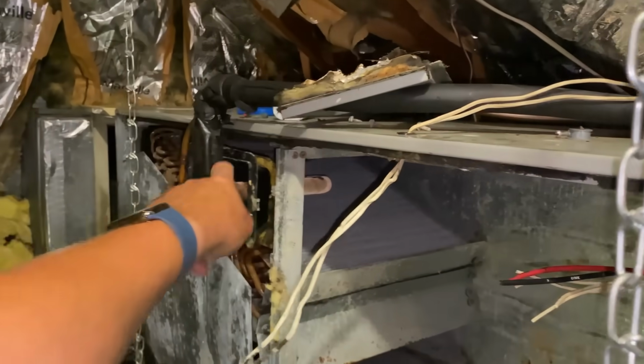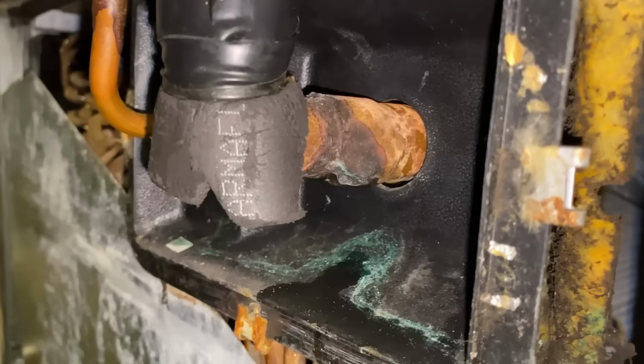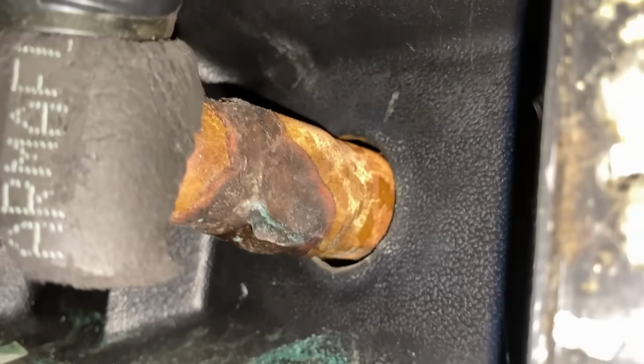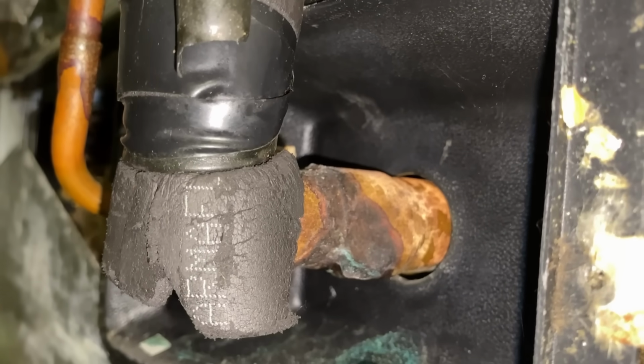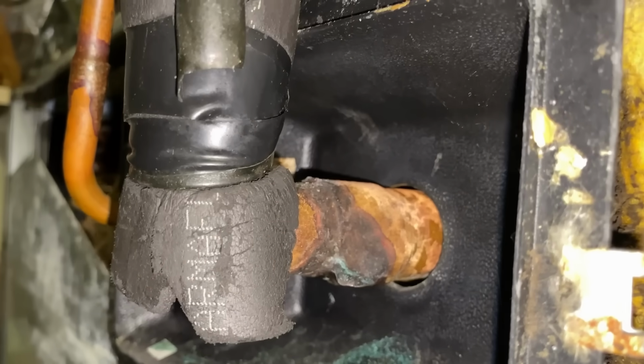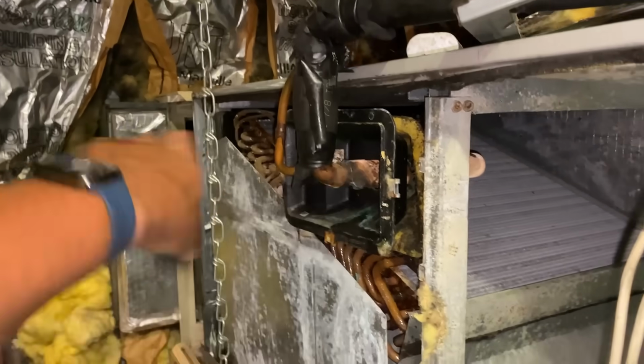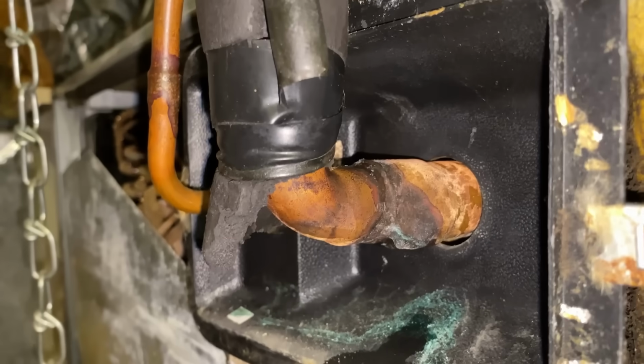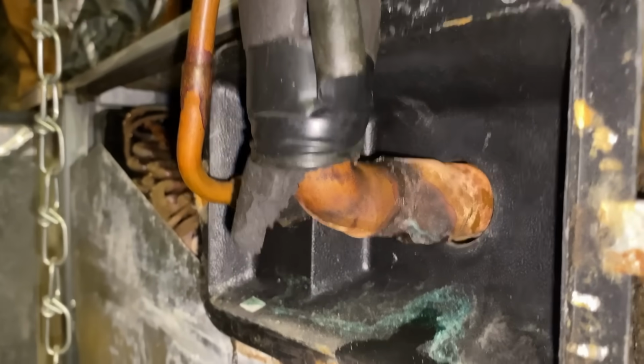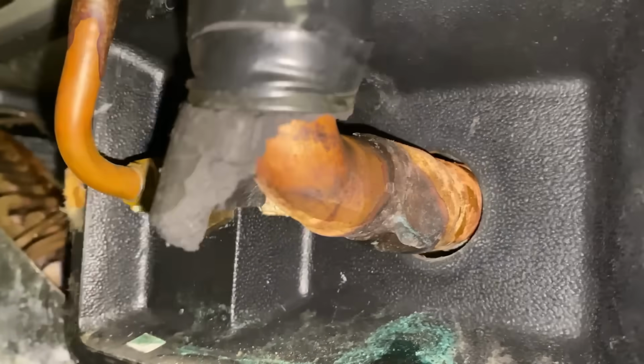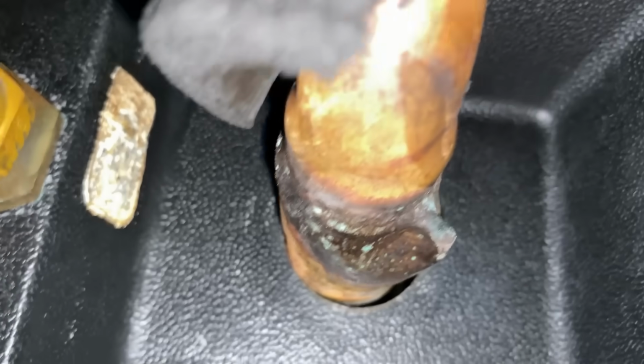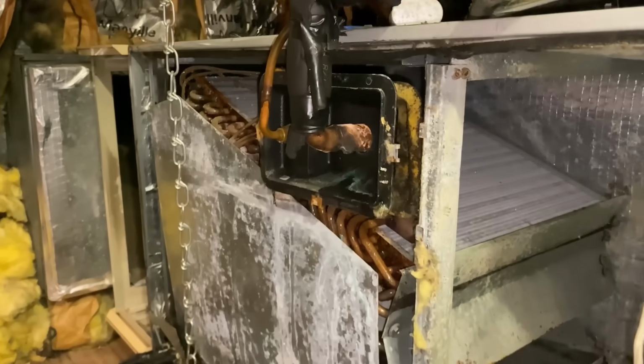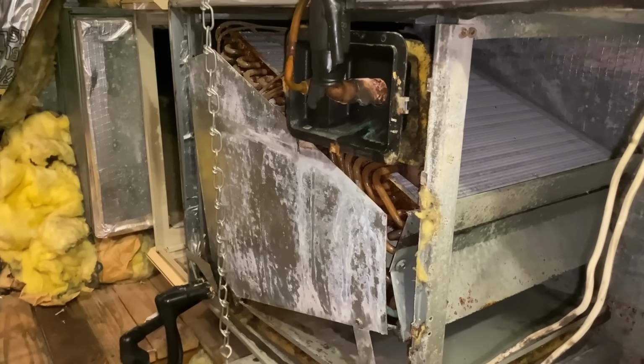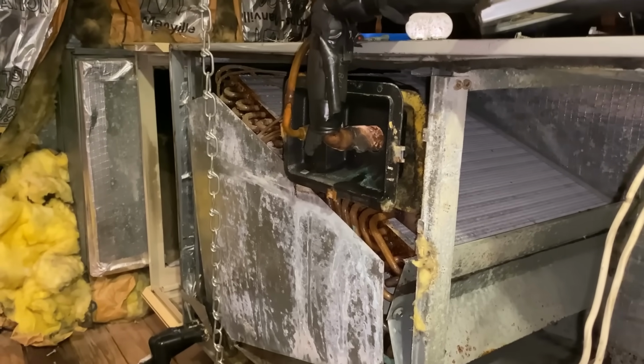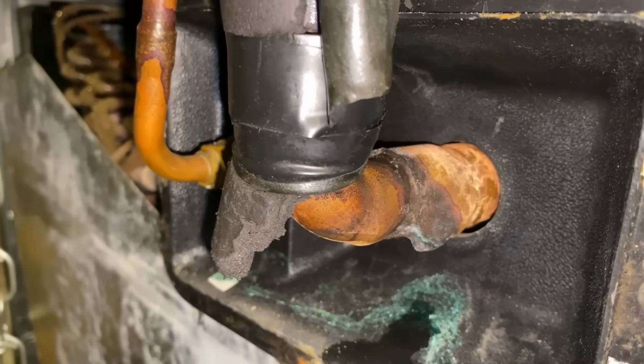Next, we're gonna cut our line set out. Did they really get that creative there? Yeah, they sure did. We had an 1 1/8 inch connection going into the evaporator coil. I guess they used 7/8, looks like a street fitting or some kind of elbow shoved in there, then crimped and brazed. Definitely got very creative during the installation process of this original air handler. Oh my God, I swear you can't make this stuff up. I haven't seen that in a while. Wow, that's crazy. All right.